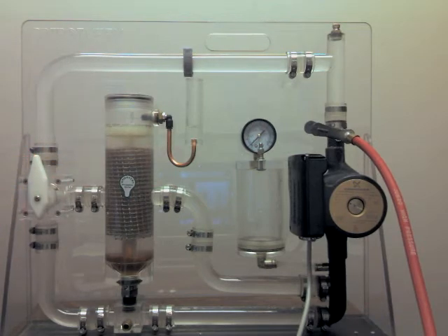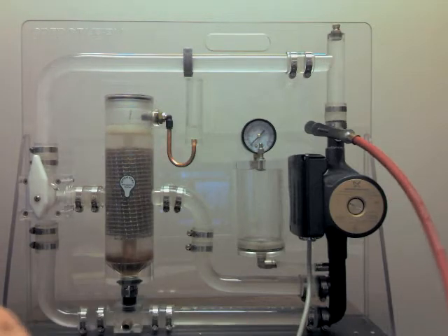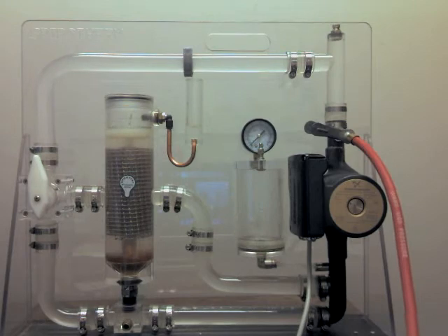Right now we're running it through the spiral vent, and what we're doing is we're bringing in the water, we're slowing it down. That's why the vessel's tall the way in that shape, and then we bring it back through again really quick. You can see just little bubbles. The big ones go right to the top. I'll put some more air in there again so you can see big slugs of air just naturally rise because it's so calm in there.